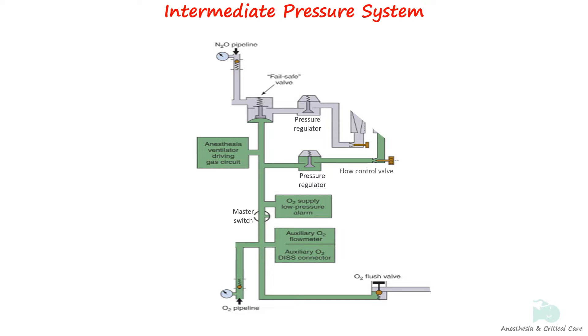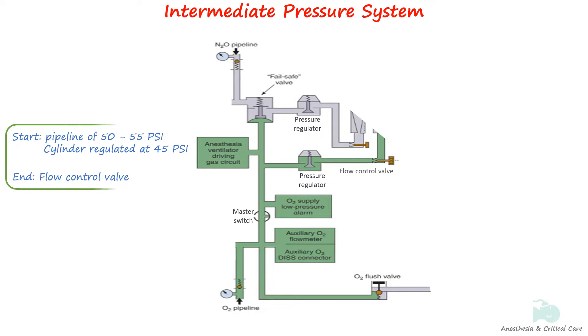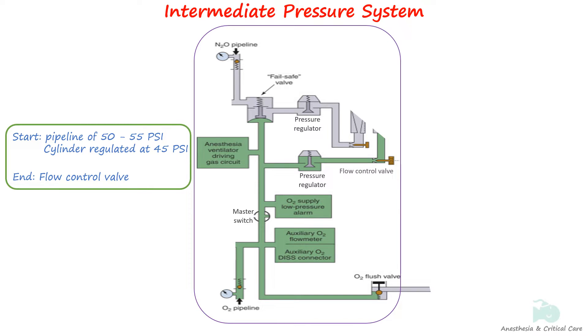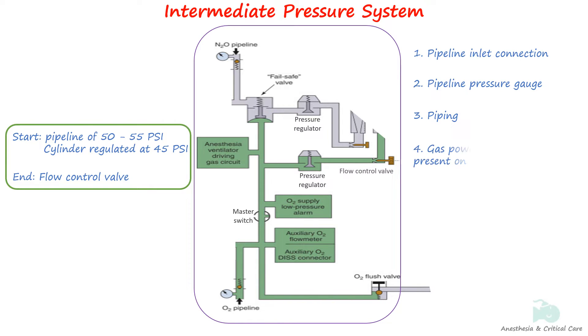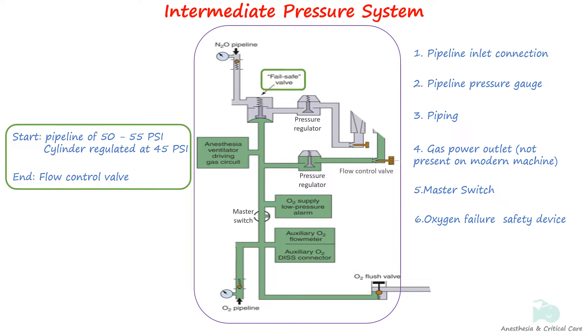The intermediate pressure system begins at the regulated cylinder supply pressure of 45 PSI and also includes the pipeline source at 50 to 55 PSI, extending till the flow control valve. It consists of pipeline inlet connection, pipeline pressure indicator or gauge, piping, gas power outlet (not present on latest machines), master switch, oxygen failure safety device, oxygen flush, and flow control valves.